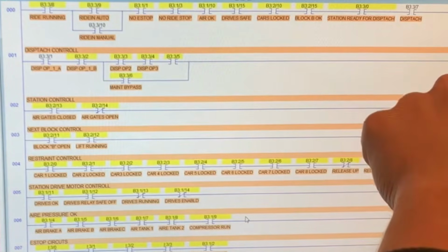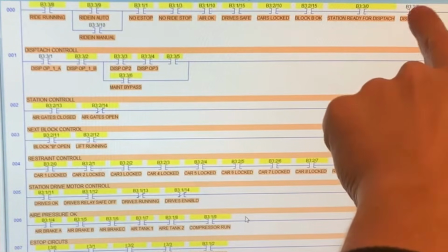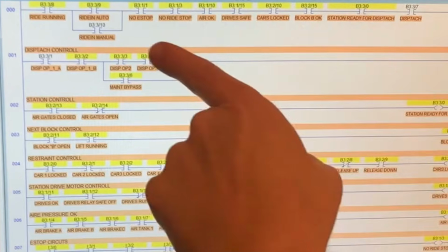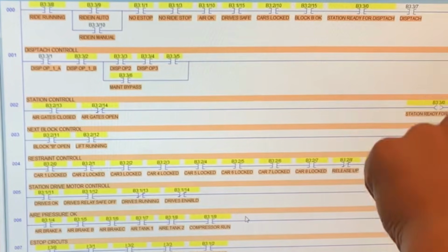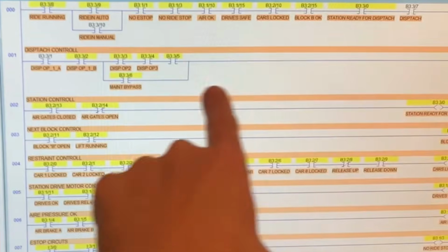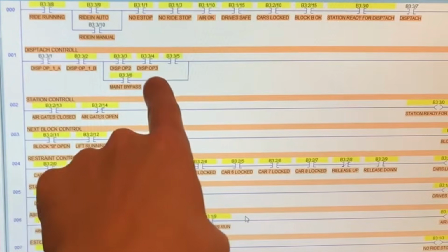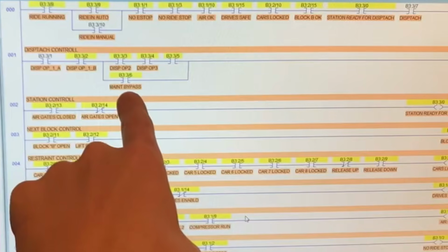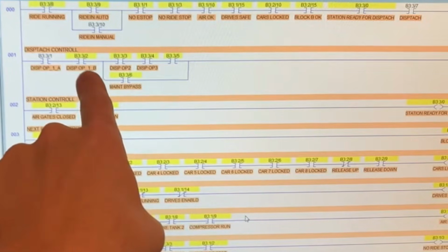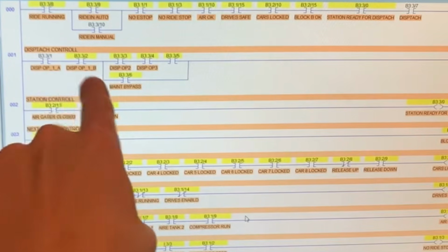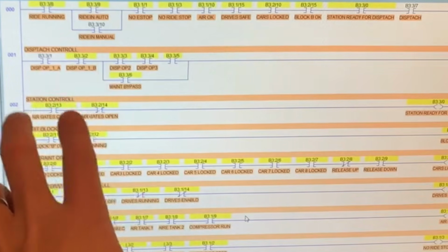The logic is typically stored inside the program vertically. It's one of the reasons why the logic is a lot of times referred to as a ladder. So it's a ladder logic style PLC. There are things like box logic and some other stuff out there, but for the most part, ladder logic, even though it's older, is still the most common thing out there. So in the program, the logic in that ladder is arranged so that the scan comes down and starts to solve each rung of the ladder.